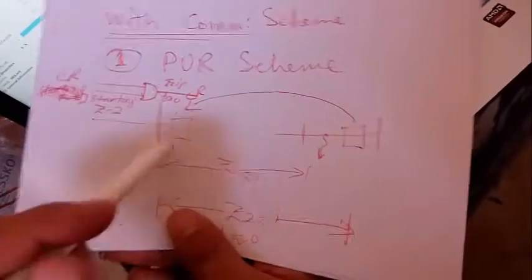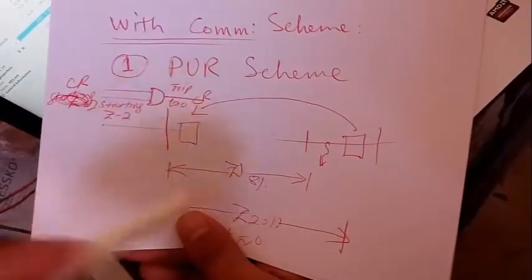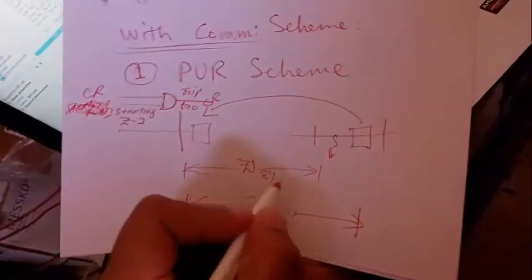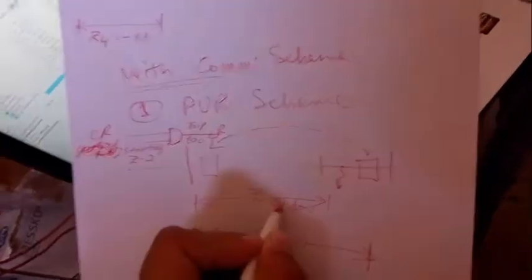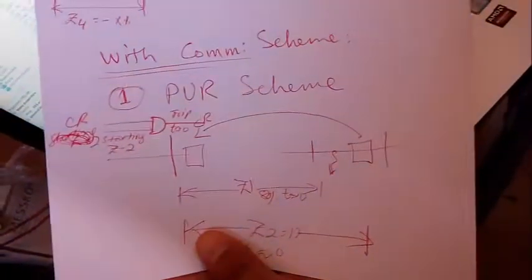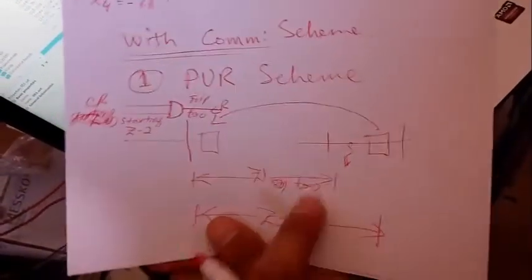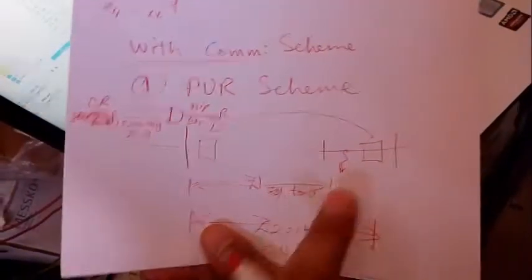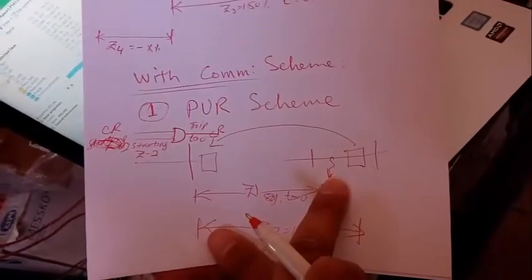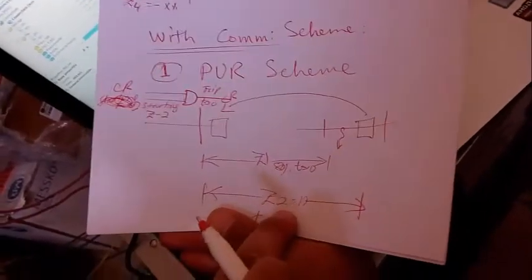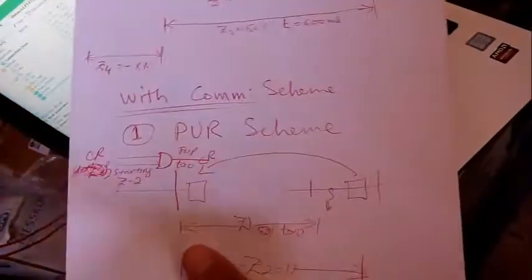In the Permissive Under Reach scheme, if a fault occurs in zone number one, it will take action at time t=0 for 80% of the line. If the fault is within the first 80% of the line, action is taken at t=0. If the fault is beyond 80%, it is sensed in zone number two.